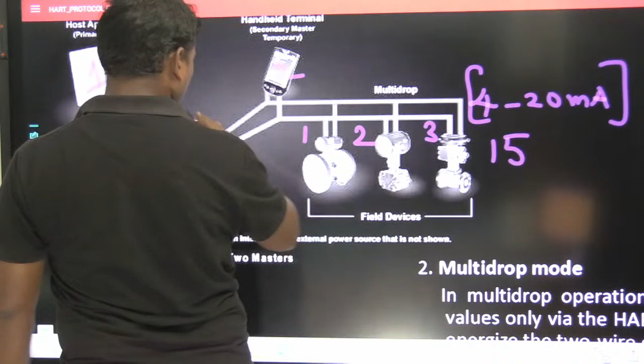That means how many devices? Up to 15 field devices can be connected. The multi-drop mode of operation requires only a single pair of wires and, if applicable, safety barriers and an auxiliary power supply up to the field devices. Do you understand? That is enough. Up to 15 field devices can be accessed by using the two masters, numbered 1, 2, 3 like this, with primary master and secondary master on the same 4 to 20 milliamperes wire. And which particular sensor the data is coming from is configurable by the master.